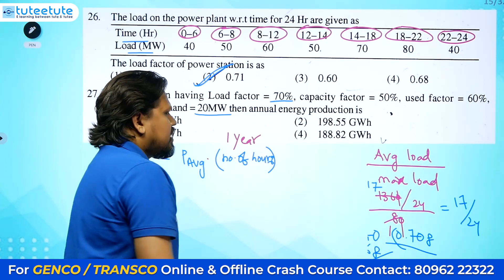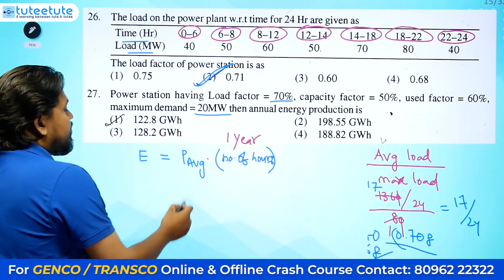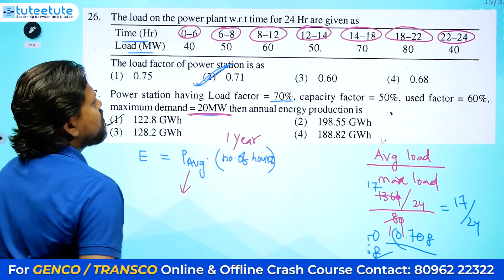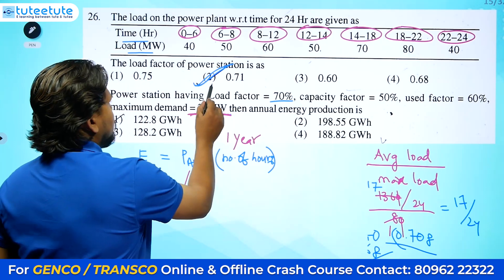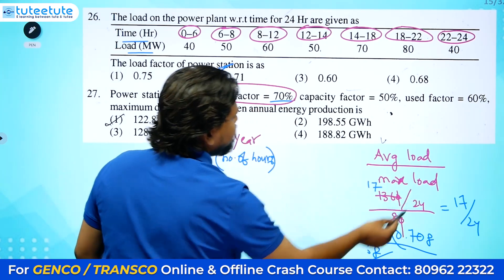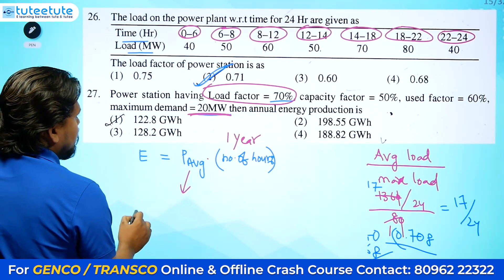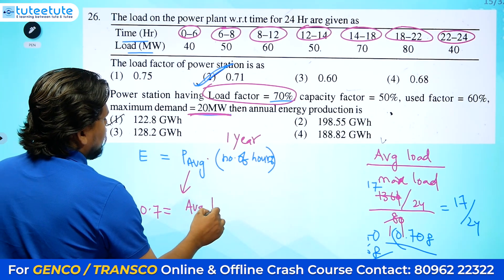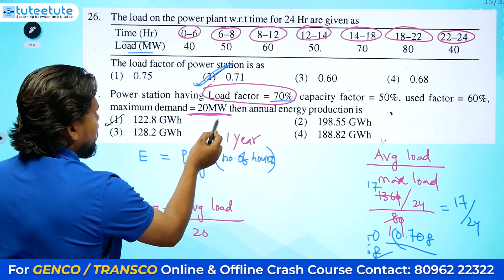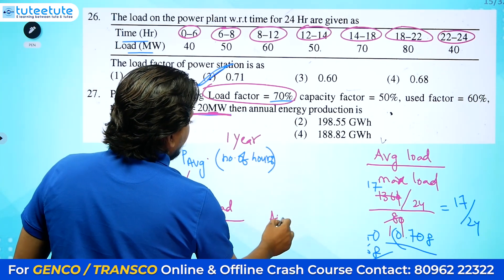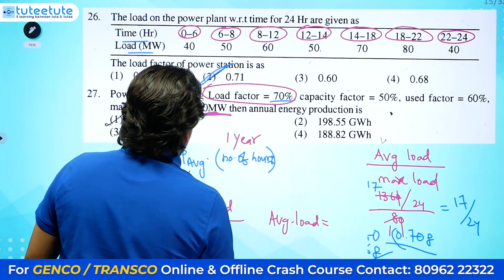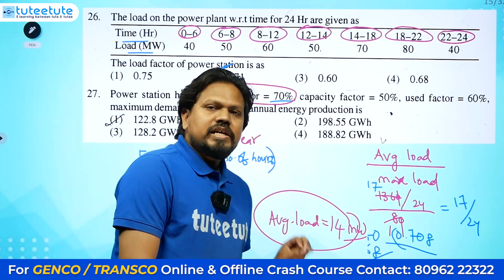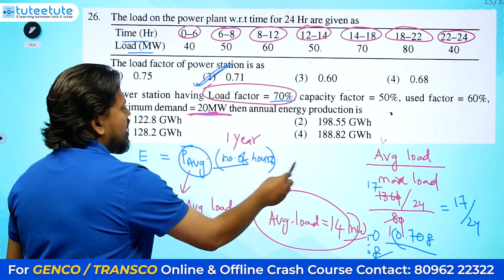Energy equals average power multiplied by number of hours. For one year, how many hours are there — that many hours you multiply. Average load: load factor = 70% = 0.7 = average load ÷ maximum load. Maximum load is 20 MW. So average load = 20 × 0.7 = 14 MW.